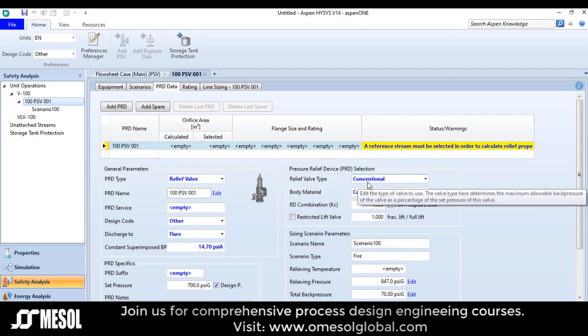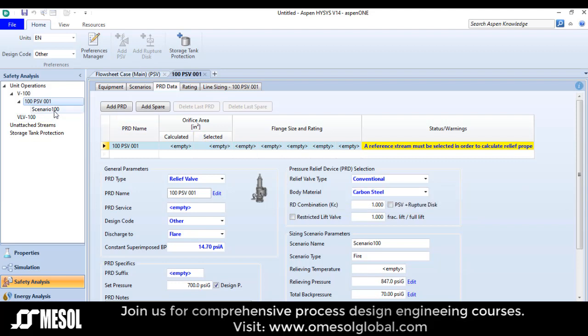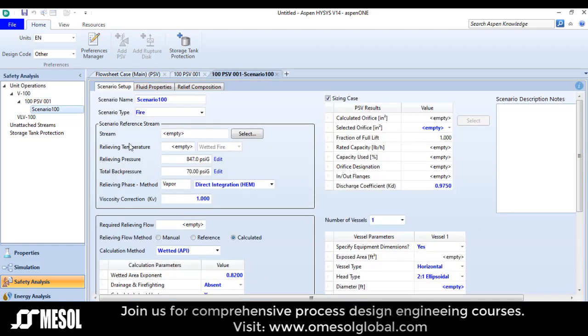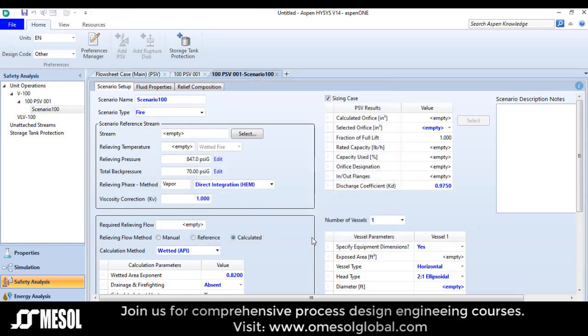The relief valve type is conventional and the body material is carbon steel. Going to the scenario option, I will select my inlet stream. My inlet stream is defined here. Click OK. The relieving phase method is direct integration, HEM. Now you can see the API model details.